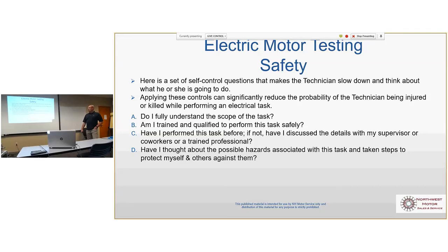Always think about the possible hazards associated with what you're doing and people around you. I went into a motor control center a couple months back after an arc flash had happened, on a pretty large medium voltage motor. The motor control center doors are designed to withstand an arc flash if all the latches are bolted down, and even though this one had bowed all the way out, there was a halogen light inside with a quartz glass front, and that glass actually melted and ran down the wall. So it's gnarly.